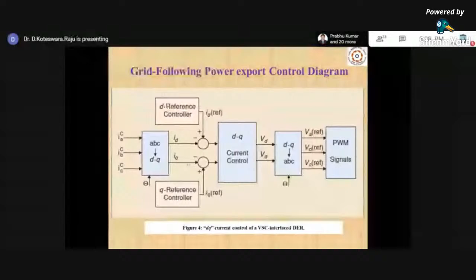We will compare with this reference control ID reference. Similarly, IQ reference is compared with the IQ. So the error signals are applied to the DQ current control loop to determine the D and Q components of the reference voltage signals. That is VD and VQ. Finally, through this VD and VQ, we are converting into ABC by using this DQ conversion. So from this, we will achieve VA, VB, and VC, three-phase reference signals for the PWM signal generator, and from this PWM signal, it will give the firing angles to the converter such that a particular power flow control will take place.